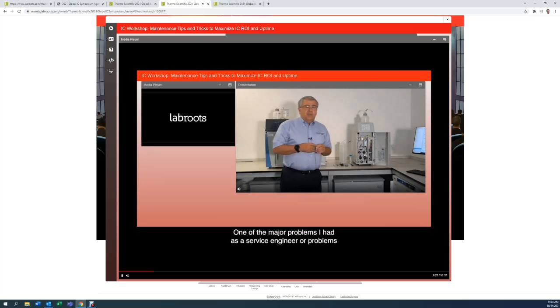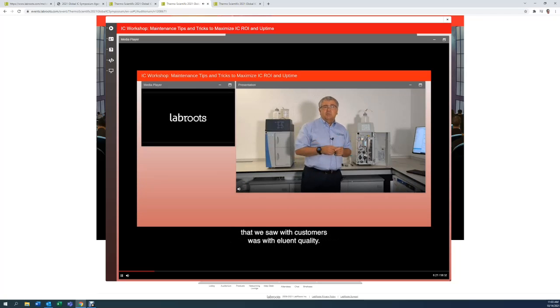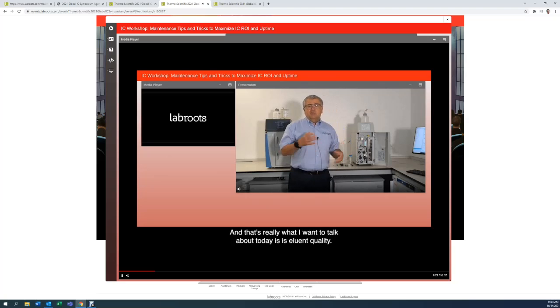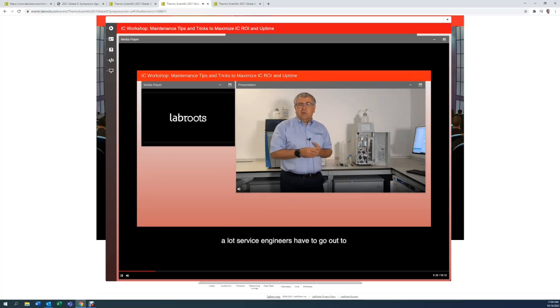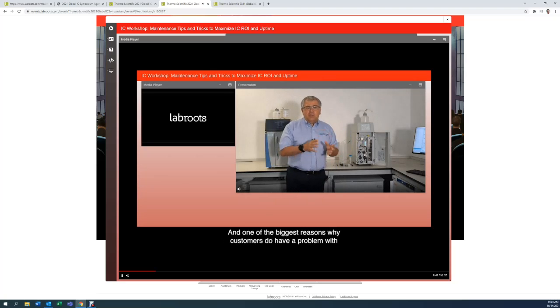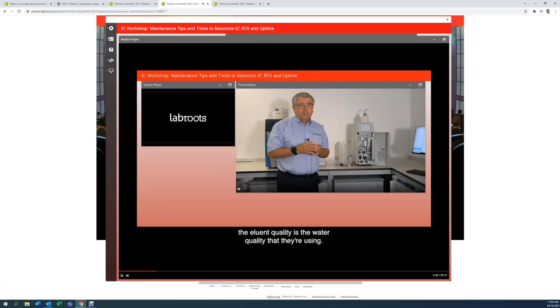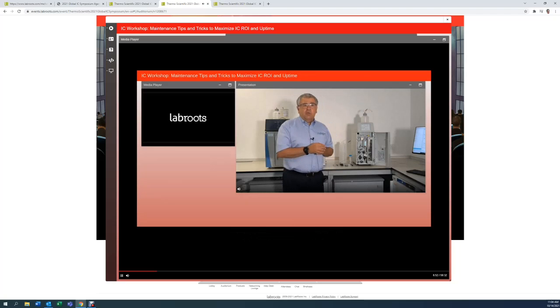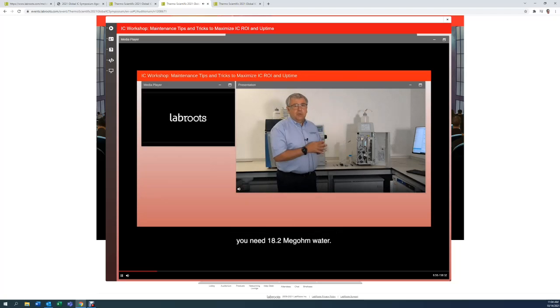One of the major problems I had as a service engineer, or problems that we saw with customers, was with eluent quality. And that's really what we want to talk about today, is eluent quality. It still causes a lot of visits. A lot of service engineers have to go out to troubleshoot customers' eluent quality. And one of the biggest reasons why customers do have a problem with the eluent quality is the water quality that they're using. To successfully achieve good ion chromatography, you need 18.2 megohm water.